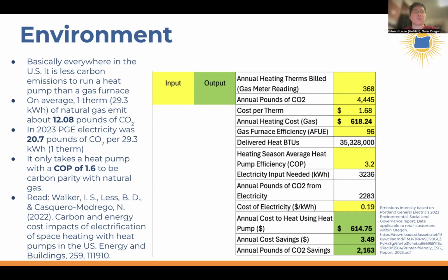You could typically get a coefficient of performance of two-ish, 2.5. Even the worst heat pumps on the market, poorly maintained, kind of old, you can get a coefficient of performance around 2.5. And modern heat pumps could easily get a coefficient of performance of 3. And so in that case, you're well into heating with electricity via a heat pump being less carbon. In the example scenario where you have a 96% efficient gas furnace, if your heat pump has a COP of 3.2, you're going to be saving about 1 ton of carbon per year.